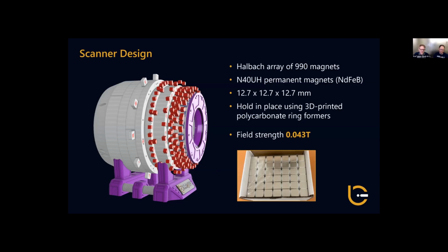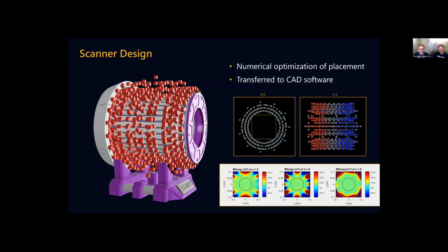Now, if we remove all these plastic parts, you can see the complete array of these 990 magnets. And the exact location of these magnets has been calculated using a software that Leo developed. And basically, the software is based on the MagPylib library to simulate the magnetic field for a specific arrangement of magnets. And then the software uses a numerical optimization procedure to optimize the location of the magnets to get a homogeneous field in the center of the magnet. And so this was used to calculate the exact geometry of this arrangement. And then later, this geometry was transferred into the CAD software for doing the 3D printing.